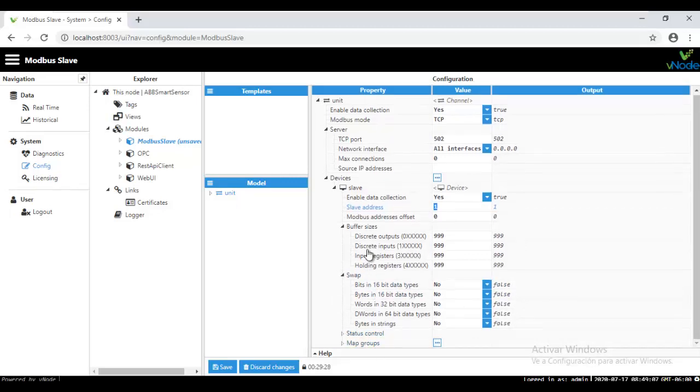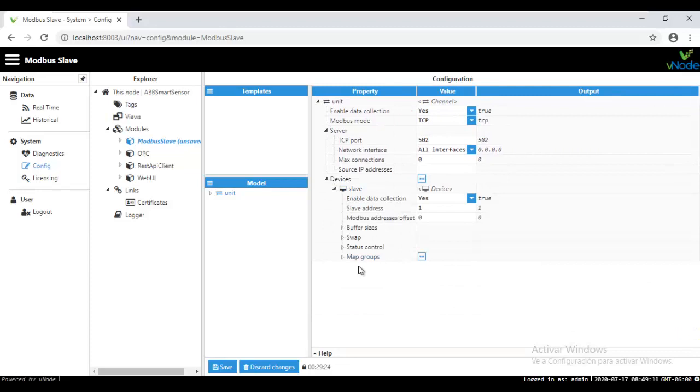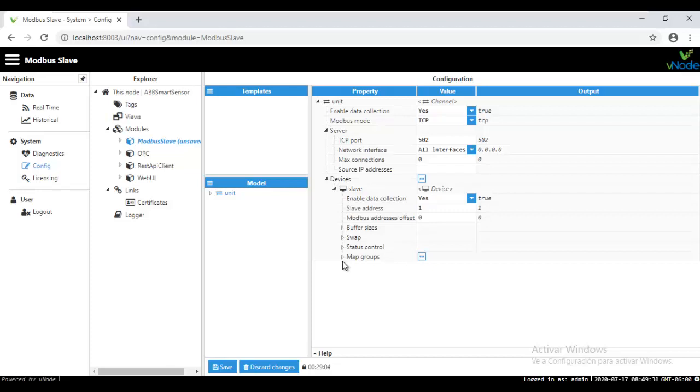And also, you are going to create in this case a map group. What is a map group? A map group is the part in which we are going to link the data source data, the data that is coming from any kind of data sources that vNode is already collecting. I don't know if you are working with PLCs, if you are working with OPC server, if you are working with databases, if you are looking to take data from sensors or any kind of device or industrial device. Once you do this, the map group will link that data with a Modbus addressing environment in which you will be selecting which Modbus register will be linked to that tag.